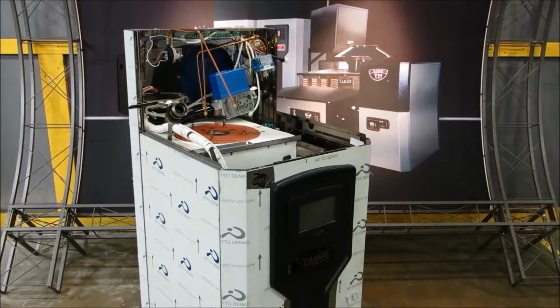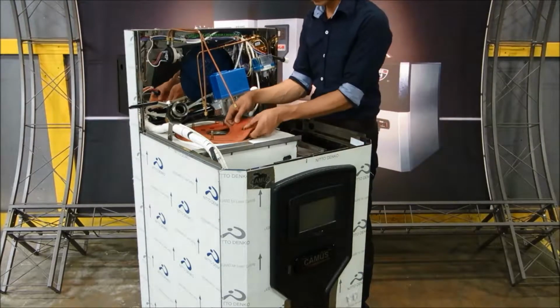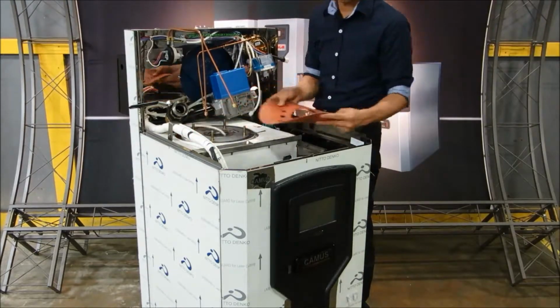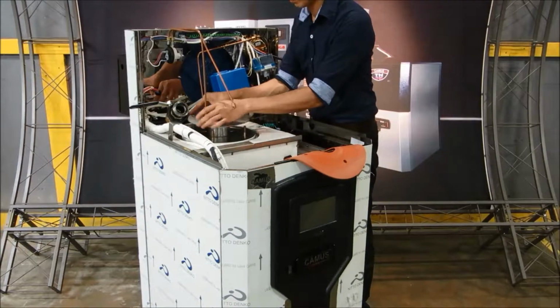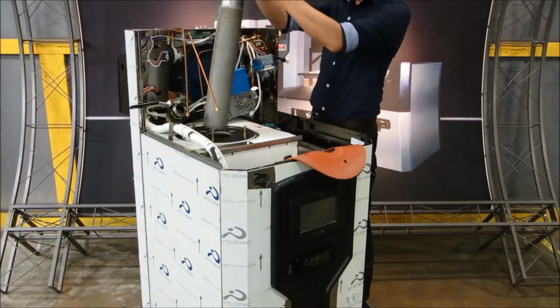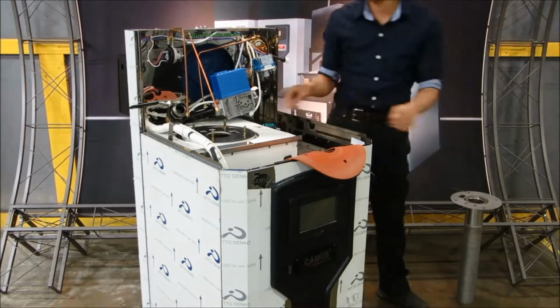Remove the red silicone gasket, followed by removing the burner. The burner must slide out vertically. Avoid tilting the burner on an angle, as that may damage the fiber mesh. Next, remove the graphite-backed ceramic gasket.